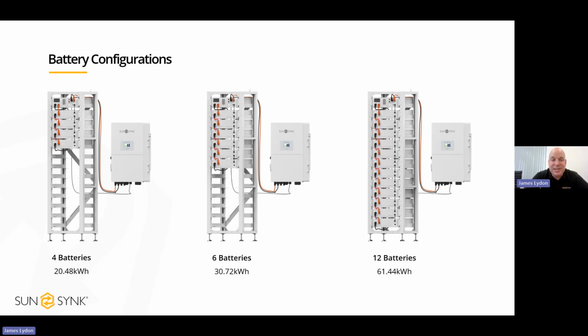So yeah, different possibilities. Someone might want to start with 4 batteries, look at some data, and then add more at a later date until they potentially get to a full rack, which is 12. But as I mentioned, the 30 and the 50 kilowatt both have 2 battery inputs. So without using bus bars, you can connect 2 61.4 kilowatt hour stacks to the 30 kilowatt and the 50 kilowatt. But again, you can use up to 16 stacks. If you're doing that, you would need bus bars, and our tech team would talk you through what that looks like in advance.